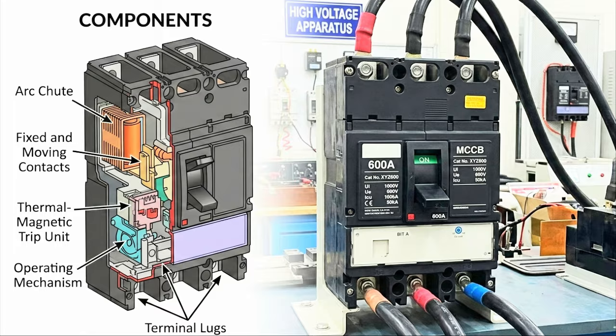Keep watching this video till the end, because we will discuss all the important things. We have a fire pump that has an issue because it does not have supply available to operate the motor. So we find what the issue is with the breaker, because it has an under voltage relay that does not allow the circuit breaker to close when there is a problem. I will discuss everything on how to find it out.